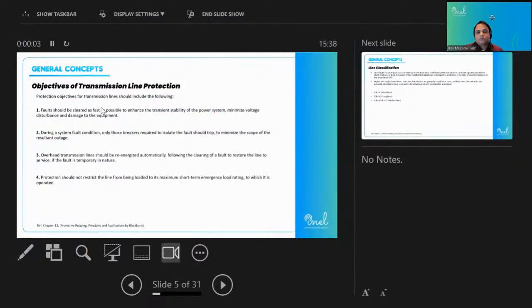And what is the objective of the protection system? Basically, we are protecting to minimize the disturbance and to protect the equipment connected with the transmission lines. If there is a fault on the transmission line, we have heavy equipment connected on both sides of it. If a transmission line is connecting generating stations to the load center, then on both ends of the transmission line there will be very costly equipment connected. So we need to protect both sides of the transmission line.